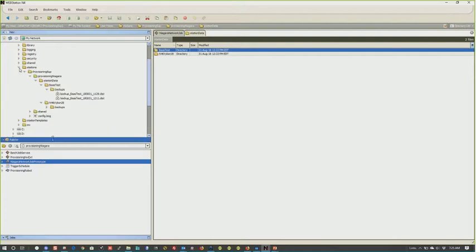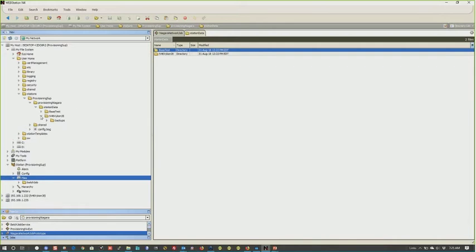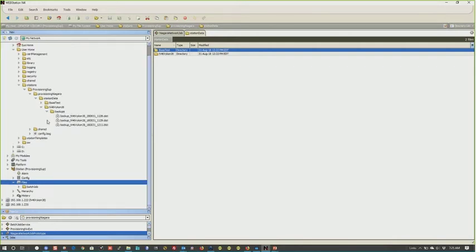So if I go up under stations, you'll see Provisioning Niagara station data, and then the JACEs, and then under there you have your backups. So that's where they get stored. So then when you do a station, if you were to go in your supervisor and do a distribution backup or a station backup, all of these are going to be part of that as well. So your station backup for a supervisor can get pretty big, especially if you also have your histories that you're collecting, that you back those up. So those get very big. And if you're trying to whittle down, you're trying to do a backup just to get off site to check or whatever, you can take that part of it out and save yourself a lot of space as well.